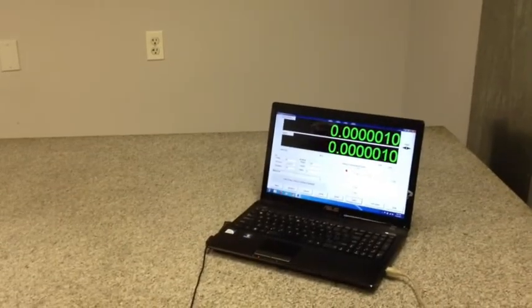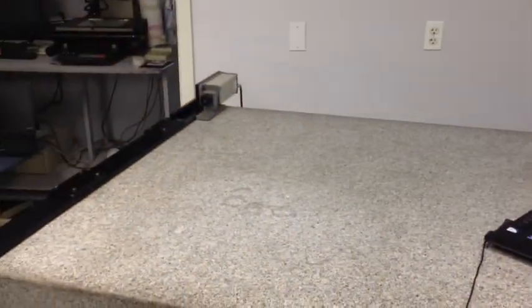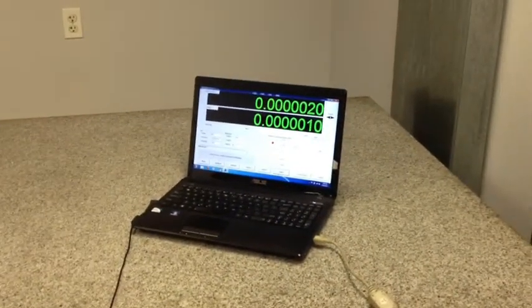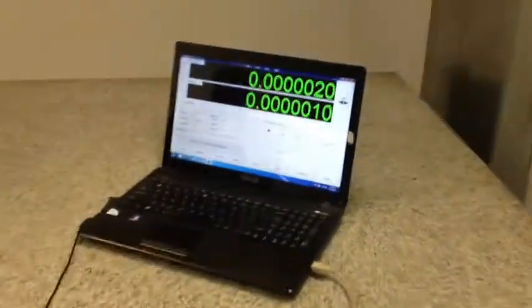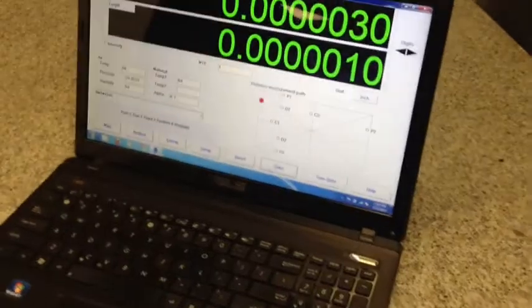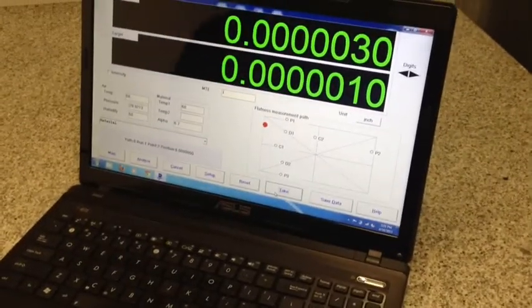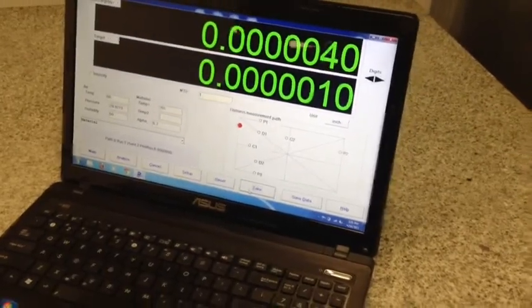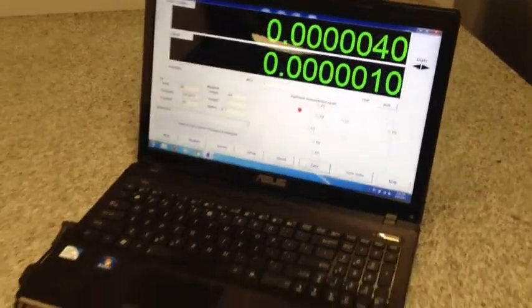Hello, today we're going to demonstrate how to calibrate a grade B 48 by 72 granite surface plate utilizing a laser. We've taken the time to already set the parameters in the software, so at this point we're ready to go. The laser has been warmed up and we're ready to begin.